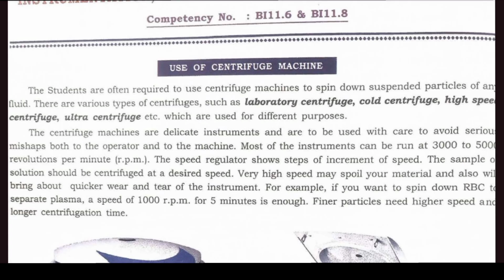The centrifuge machines are delicate instruments and are to be used with care to avoid serious mishaps both to the operator and to the machine. Most of the instruments can be run at 3000 to 5000 revolutions per minute. The speed regulator shows steps of increment of speed. The sample of solution should be centrifuged at a desired speed. Very high speed may spoil your material and also will bring about quicker wear and tear of the instrument.